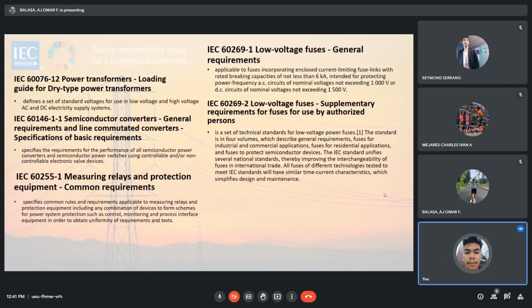Next is IEC 60255 Part 1, Measuring Relays and Protection Equipment, Common Requirements. All measuring relays and protection equipment used for protection within the power system environment are covered by this standard. Which in such cases shall take precedence for special applications, for marine, aerospace, explosive atmospheres, computers, etc. The general requirements within this standard may need to be enhanced by additional special requirements. The requirements are applicable only to relays in new condition. All tests in this standard are type tests, unless otherwise declared.